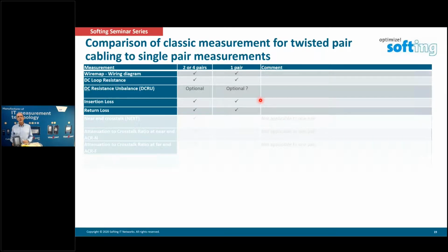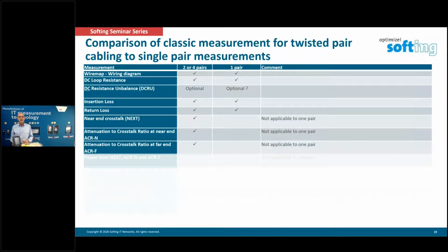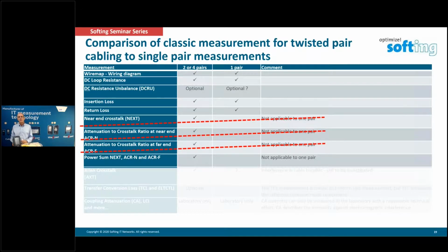Insertion loss is an important parameter, and return loss. Near end crosstalk and all the measurements related to crosstalk - attenuation, ACR, attenuation to crosstalk ratio near end, and attenuation to crosstalk far end - cannot be measured on a single pair cable. There's no crosstalk, so they go away. Then all the power sum values from next, ACRN, and so on are also irrelevant because there's no crosstalk.